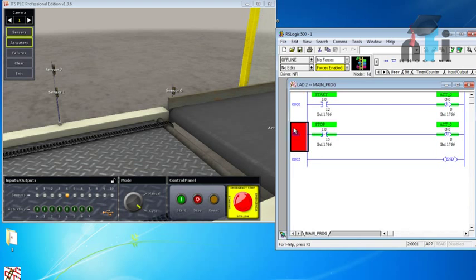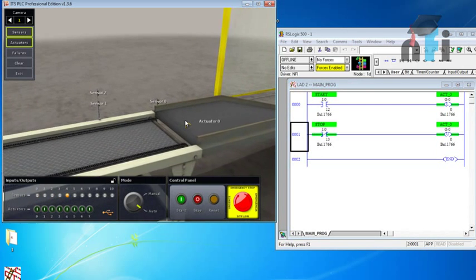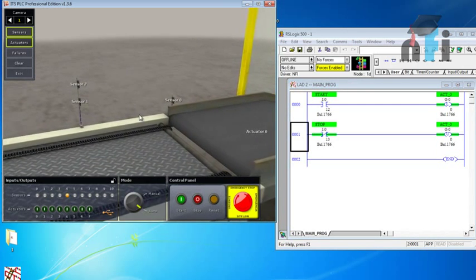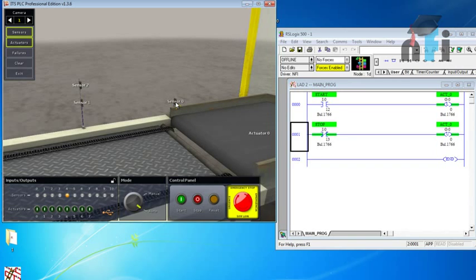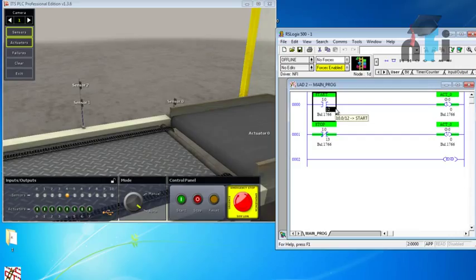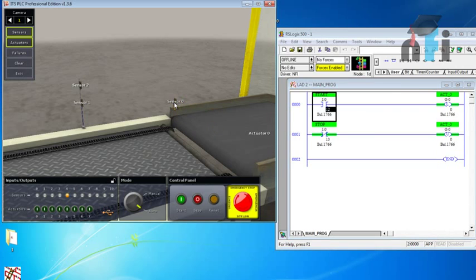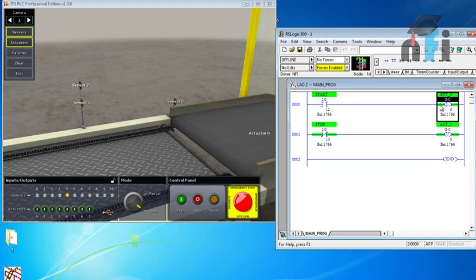Let me go offline. Generally when you play around with sensors and take the sensor signal to turn on the output, we usually take the rising edge, which makes the program very easy to follow and troubleshoot. Rising edge means it's a bit which will be on for just a moment - suppose the sensor is on for five seconds, but you need just a single pulse when the sensor turns on.